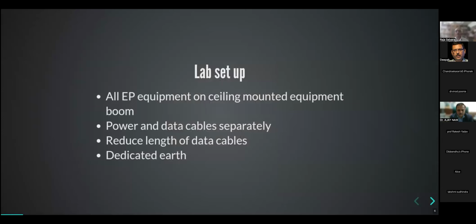Try to identify which cables are carrying signal data and which are carrying power, and see that these are kept separate. Paying attention to small things like this when setting up the lab helps with having better signals and a relatively noise-free lab. So keep data and power cables separate. If they have to cross, they should generally be perpendicular to each other. Whenever cables lie parallel to each other or are coiled together, they tend to have more interactions. If cables are going perpendicular to each other, the interactions are less.